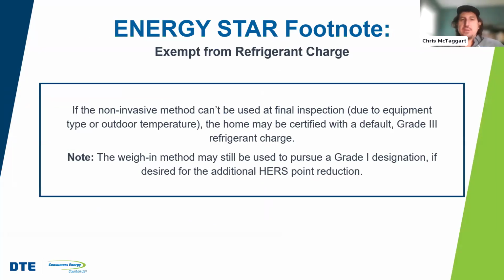So there is an exemption on refrigerant charge if the non-invasive method can't be used at final due to equipment type or outdoor temperature. So when we say equipment type, so variable refrigerant flow equipment, like a lot of modern heat pump systems, you cannot use the non-invasive method for verification of refrigerant charge. So if you have one of those systems, say you have an inverter heat pump that's installed, the rater cannot use the non-invasive method.